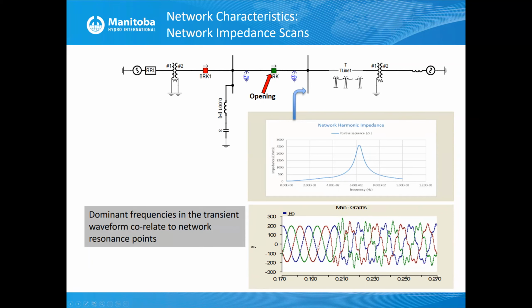Now, if you trip the circuit, what you'll see is that this 12th harmonic will be shown in the transients, okay? Now, take the assumption where you are trying to connect the wind farm or any power electronic device to your system, okay? If that power electronic device injects or takes in 12th order harmonic, or the controls of the wind farm can take in 12th order harmonic, it can amplify the resonance and cause major problems. Okay, so network resonance is extremely important. Network characteristics are extremely important because they can cause many problems to your inverters.